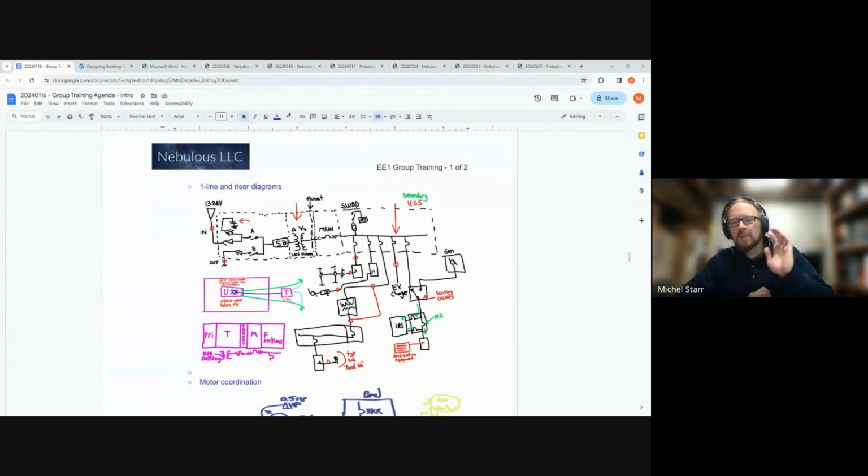The ratings that happen on the panel schedule are there because they end up being branch circuit devices. It's the person operating the CAD program or BIM program at the designer level, versus maybe somebody who is overseeing the facilitation of the one line. So those details aren't always scrutinized until the design gets to final, but even then they aren't. So matching up the details on the panel schedule to the one line is difficult.